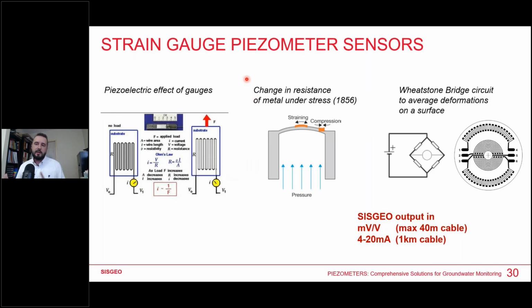We have two main technologies in Sisgeo. We produce strain gauge piezometer sensors and vibrating wire piezometer sensors. So what is the difference between strain gauge and vibrating wire? Strain gauge uses the piezoresistive effect of gauges. What does it mean? Piezo, remember, etymologically means to press. So you use some copper foils, and their resistance changes whenever you press on them, whenever there is a force applied on them.